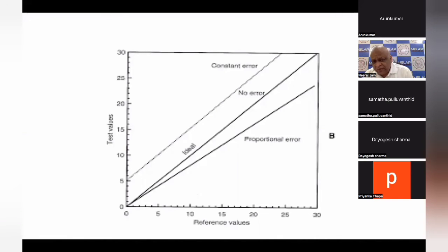And if we put this data, there is a calculator on the Westgard website. If we submit this data to that calculator on the Westgard website, we get an R value, that is the correlation coefficient. It should be as close to 1 as possible. If it is more than 0.9, this is good correlation, and more than 0.95 means excellent correlation. It should be as close to 1 as possible. So these also you need to calculate, and this you have to include in your IQ, OQ, and PQ, which we will discuss.